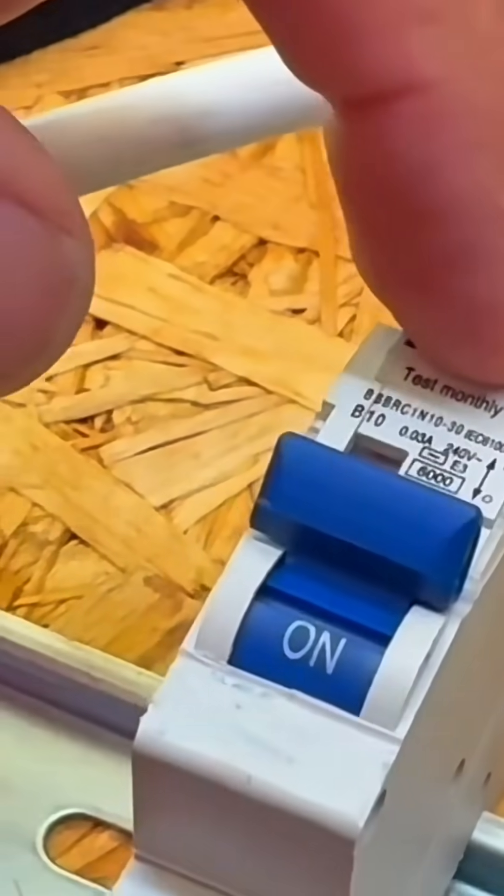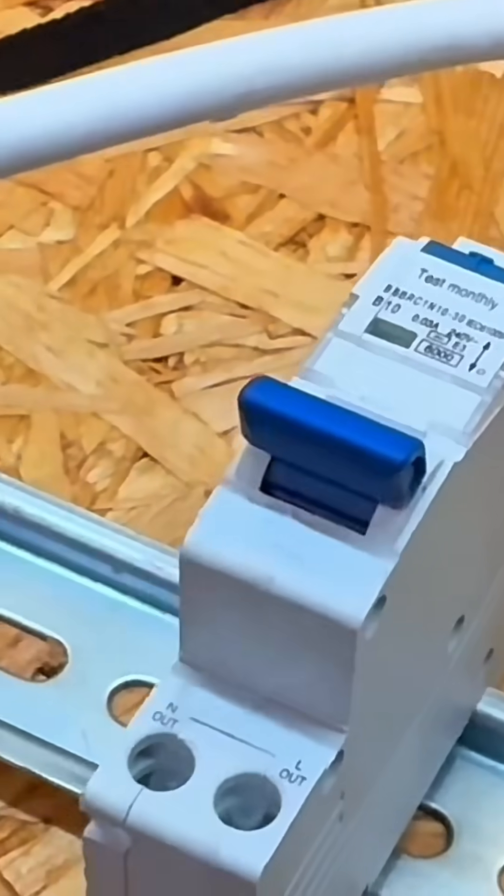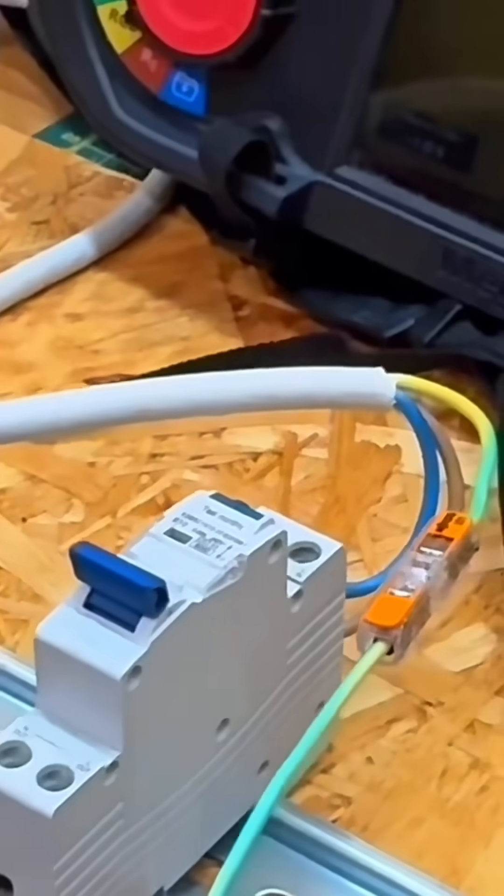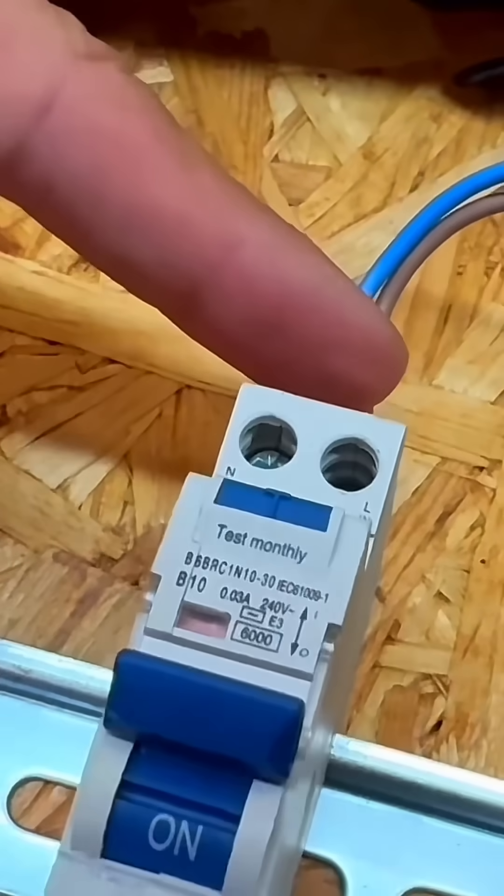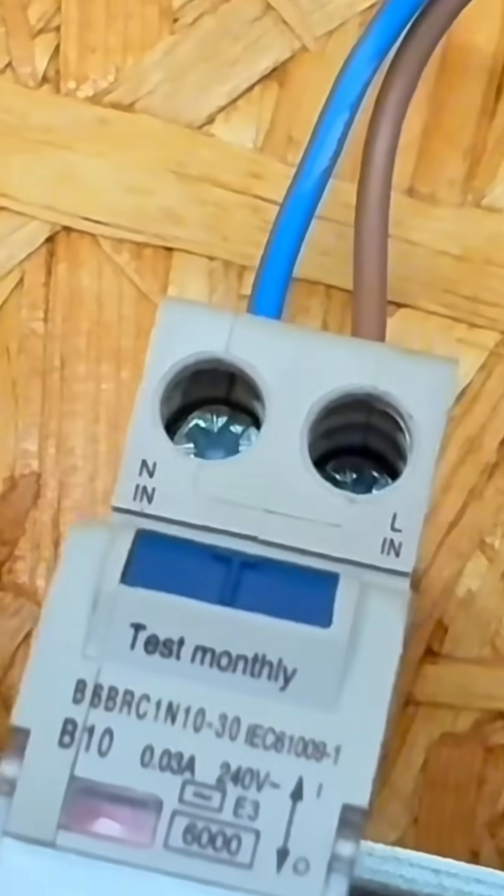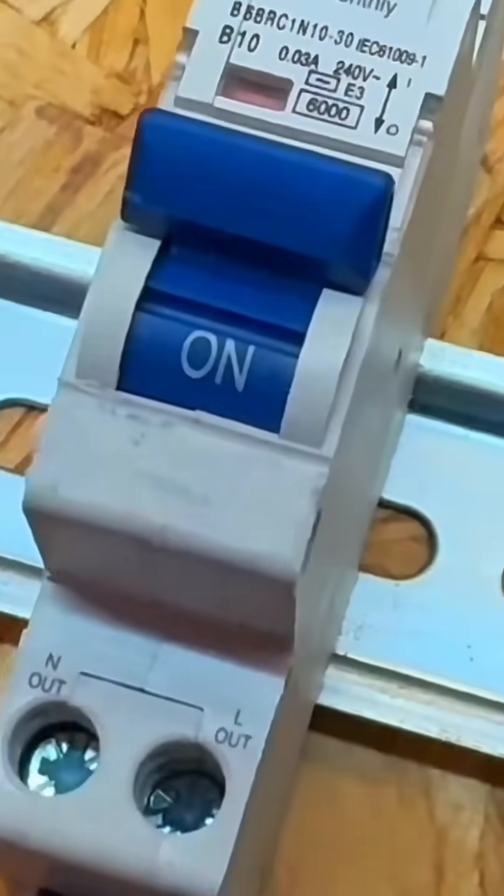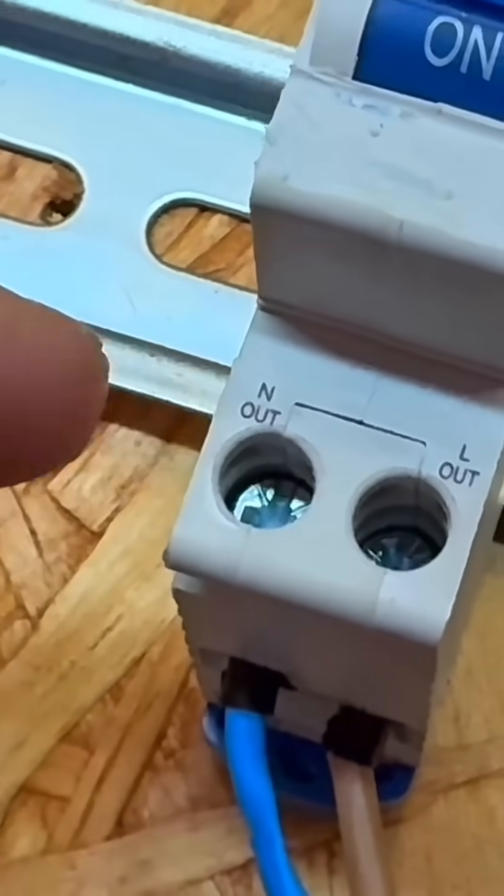Push the test button... oh, and that was a big jump there, we're not quite happy with that one. To wire this RCD up, we've got the incoming at the top here, following the manufacturer's instructions. See the in terminals there and the out at the bottom, slightly different to the ones you're used to seeing in consumer units.